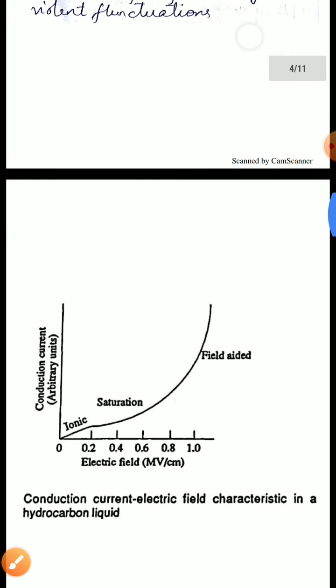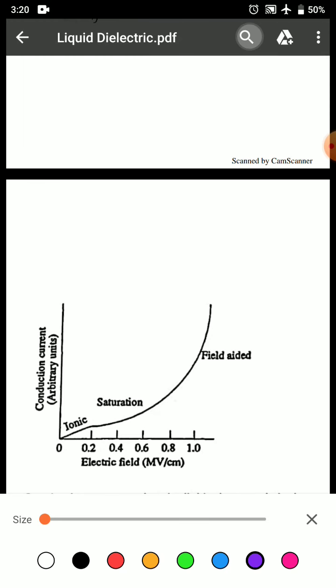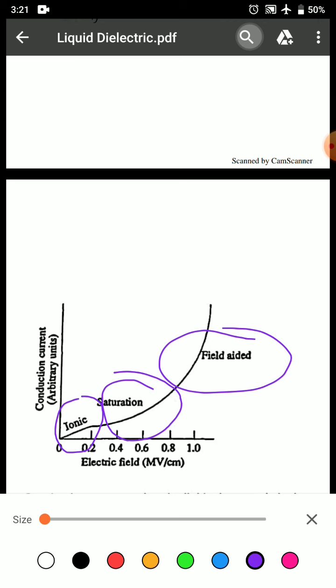Let us see a graph which explains about conduction current electric field characteristics. The curve has three distinct regions. At very low field, current is due to dissociation of ions. With intermediate fields, current reaches saturation value, and at high field, current increases because of field aided electron emission from cathode, which gets multiplied in the liquid medium by a Townsend type of mechanism. The increase in current by this process causes breakdown.